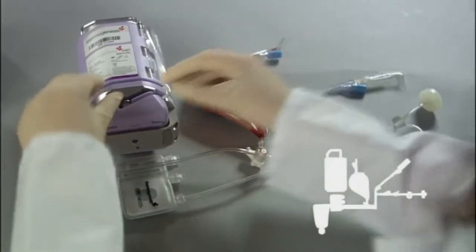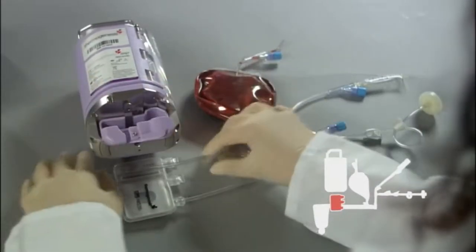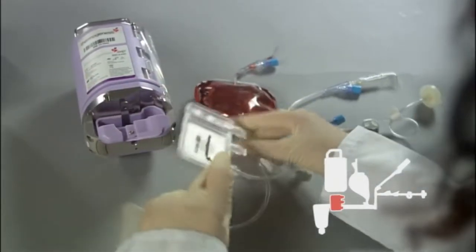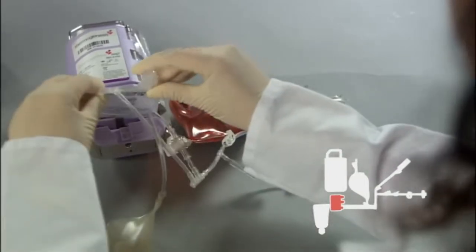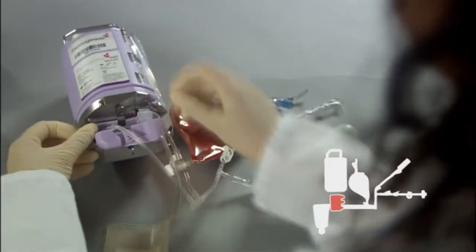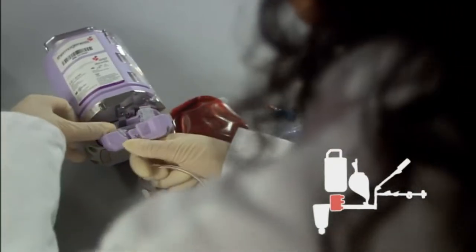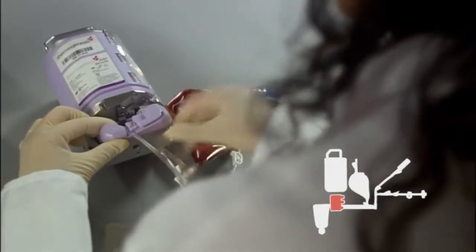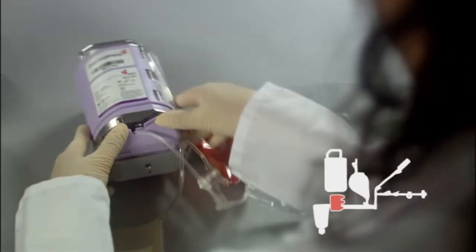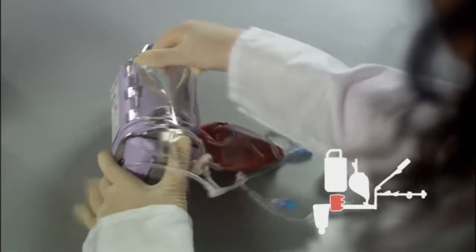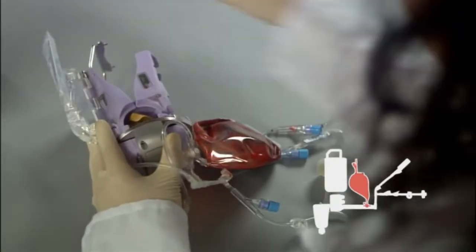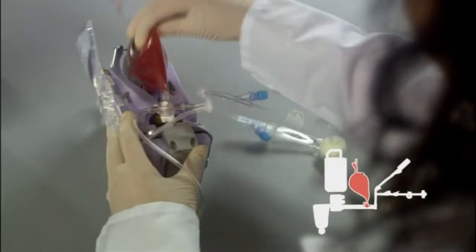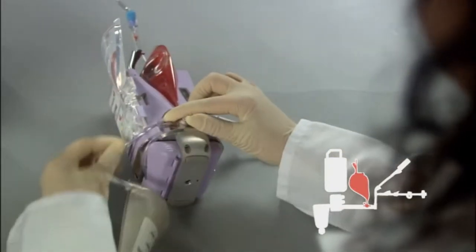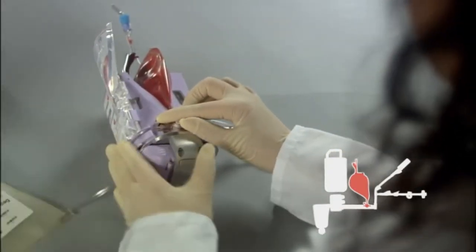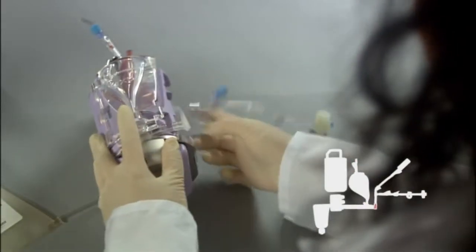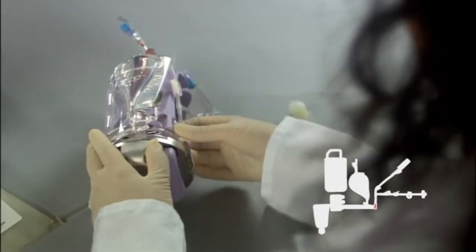Open the freezing bag carrier door. Fold the minor compartment of the freezing bag over the major compartment and place it inside. Carefully position the tubing, ensuring that the port flanges are properly in place. Close the door. Upon closing the door, you should hear an audible click. Turn the device and open the large clear door. Place the processing bag into the cavity and the valve into the valve actuator cuff. Secure the F fitting. Close the clear door and turn the device so that the RBC bag cavity is facing you.